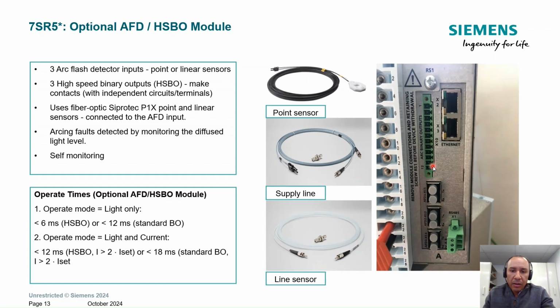and also this green connector here, that's the high speed binary outputs. Okay, there are 2 types of sensor. One sensor is the point sensor. With the point sensor, usually we protect the cable compartment. We put one facing up inside the cable compartment and one facing down, so you can overlap the region of protection inside the cable compartment. Also, we have the line sensor. These are naked fiber, and with this line sensor you can go up to 40 meters, 20 meters to go on the bus bar and 20 meters to return on the bus bar, so that you can protect the bus bar. The point sensor is more local and more centralized, for the cable compartment, and here that's for the bus bar protection.